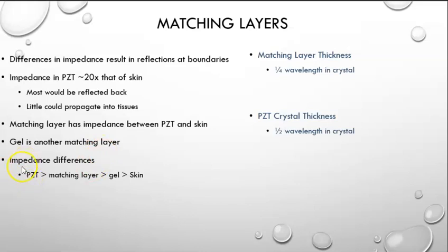So when we look at the impedance differences, we see that the PZT has the greatest impedance, the matching layer is next, then the gel, and then the skin. And it's very important that we have this matching layer be exactly 1/4 wavelength thick, and that's for geometrical purposes, and we're not going to worry about why that is. We're going to memorize that the matching layer is 1/4 wavelength thick, just as the PZT crystal is a 1/2 wavelength thick. These are just numbers you're going to have to remember.